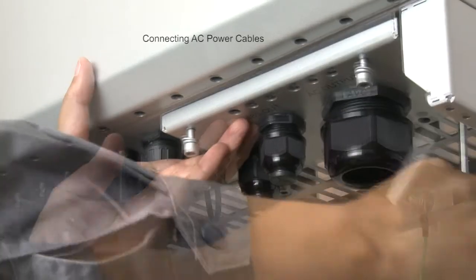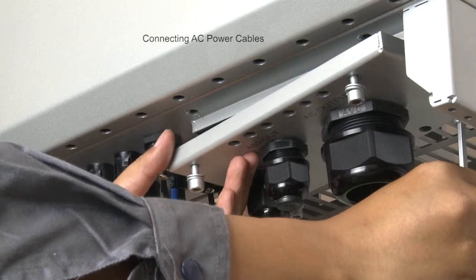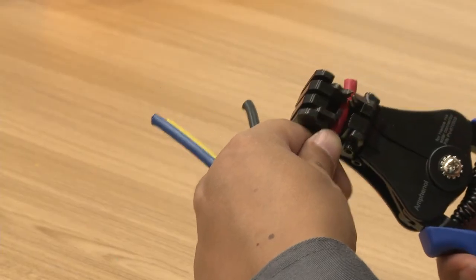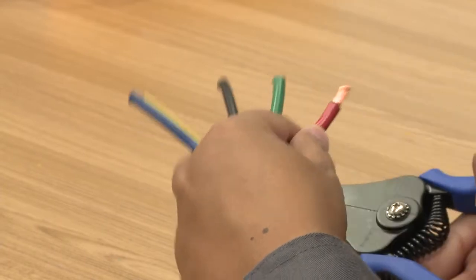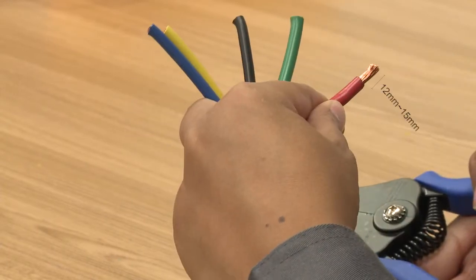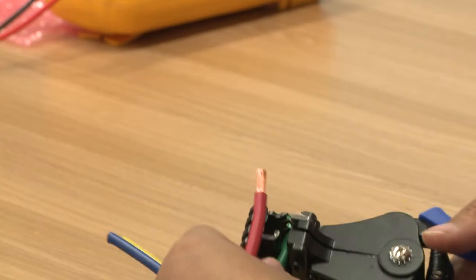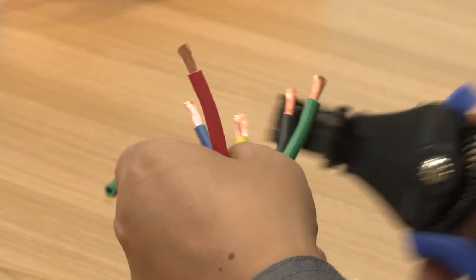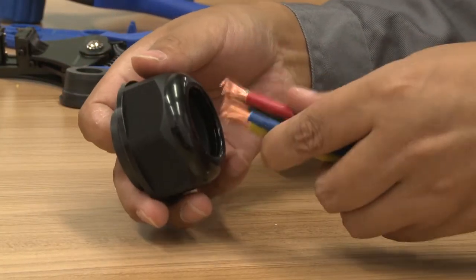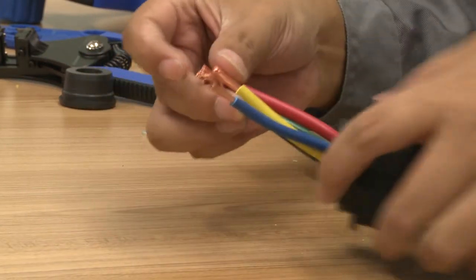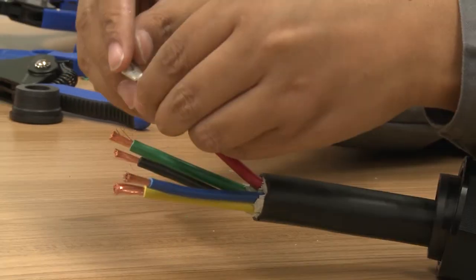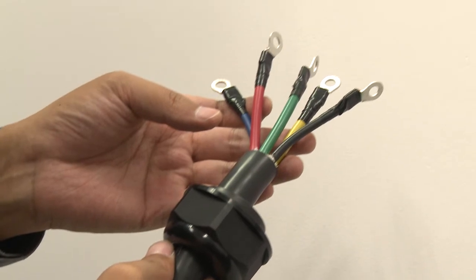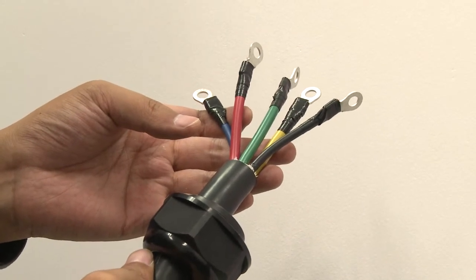Remove the AC cable board using the socket wrench. Remove an appropriate length of the jacket and insulation layer from the AC output cable, and then remove insulation from each of the inner wires using a wire stripper. Pass the exposed wire cores through the waterproof connector and crimp them to the OT terminals using the crimping pliers. Wrap the crimped wire areas with heat shrink tubing.